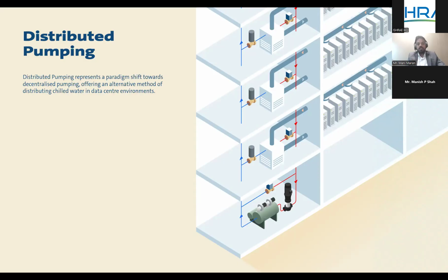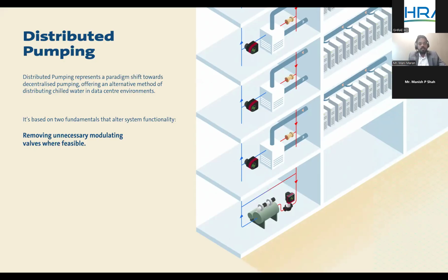If we can control the flow without the valve, then we are eliminating the unnecessary pressure created in the system, which is added as pump head and in turn consumes energy. That's what we are trying to do with distributed pumping. We are trying to change two fundamentals of a traditional system. The first is removing unnecessary modulating valves wherever feasible. Today we have valves to balance and modulate the flow in the closed loop system, and that is what we want to change. The unnecessary friction created by the valve in performing this function can be avoided in a much better way.